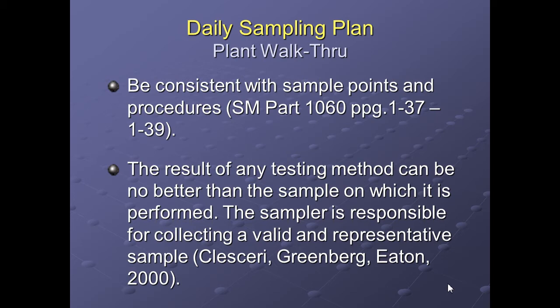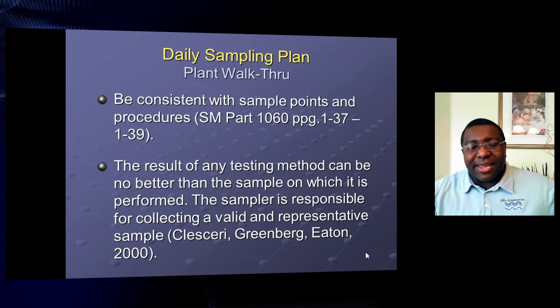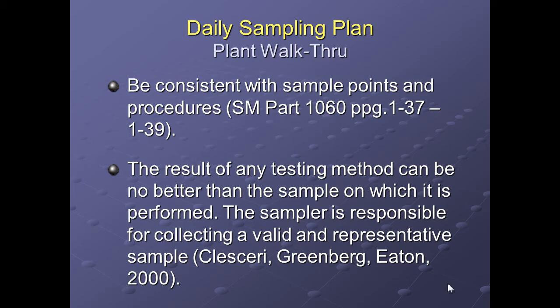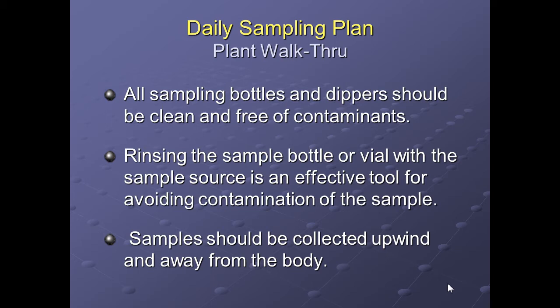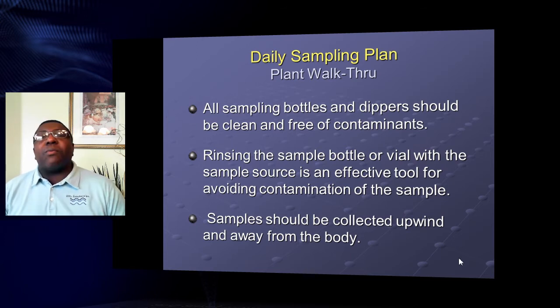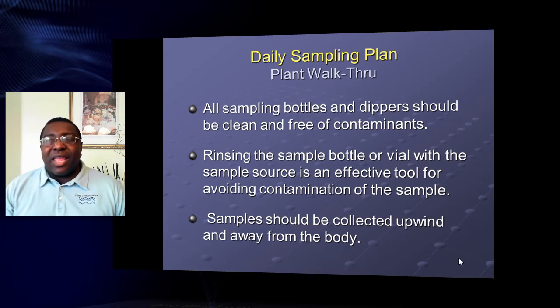Observe conditions in process areas while sampling. If something is out of the ordinary — unusual heat, cold, construction dust — write it on your sample sheet, because it may explain why a sample reads abnormally. Be consistent with your sample points; this is noted in Standard Methods Part 1060. An important statement from that section: the result of any test method can be no better than the sample on which it was performed. The sampler is responsible for collecting a valid and representative sample.